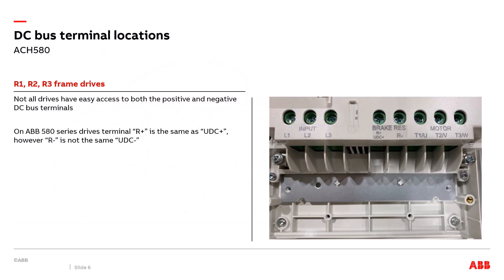So now where do we physically land our voltage probes to measure the DC bus on the drive? Well that can depend on the actual brand and model of the VFD. On the ABB ACH 580 series drives, the smaller horsepower include the R1, R2, and R3 frame drives. Access to both the positive and negative DC bus are not right next to each other. Access to the positive DC bus as shown on the image on the right red oval is the point UDC plus. The terminal to the right of it labeled R minus is not the same as the negative DC bus. That's part of the brake chopper circuit. We'll cover in the next slide where to access the negative DC bus terminal.